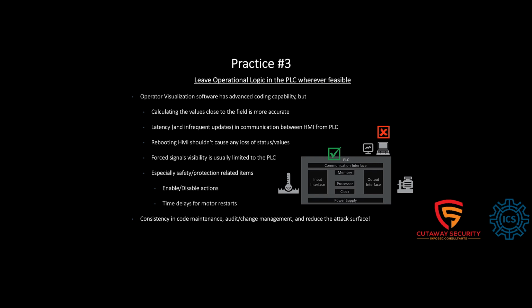And then rebooting the HMI shouldn't cause any loss of status or values. But that happens if you have code in the HMI and then you restart the HMI because there's a Windows update or some kind of patching that you did. That shouldn't cause any effect, but that's what happens if you put code in the HMI. And then force signals. The PLC could have some force signals that make it not possible for the HMI to act, but it wouldn't know if the code is in the HMI.